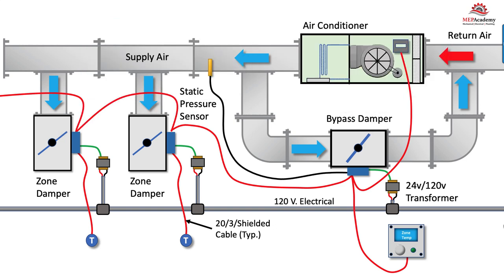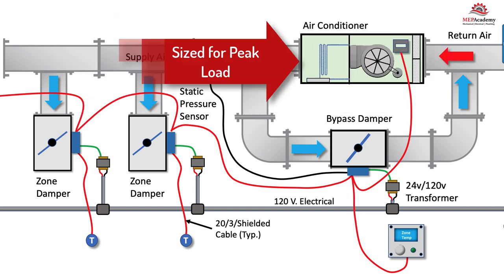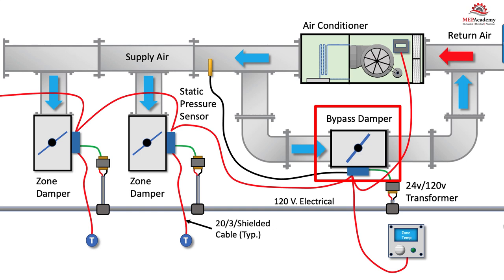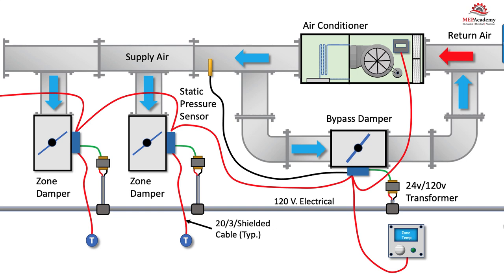The air conditioning unit is sized to handle the peak load, which is only needed a few times a year. The excess air needs to be bypassed and rerouted from the supply back into the return air system. The use of a bypass damper allows for the use of less expensive constant volume units compared to a VAV system. The bypass damper must ensure the constant volume unit receives the minimum amount of airflow required to function properly — if the minimum amount of air is not allowed over the coil, the coil could freeze up.